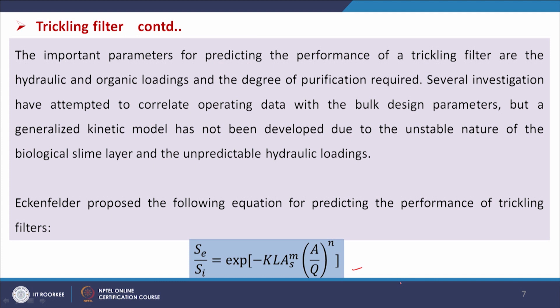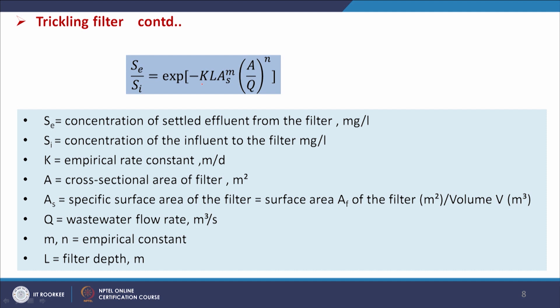Here we will see one empirical relationship proposed by Eckenfelder for predicting the performance of a trickling filter. The equation is: Se/Si = exp(−K × L × As^m × A/Q^n), where Se is the concentration of settled effluent from the filter, Si is the concentration of the influent to the filter, K is the empirical rate constant in meters per day, A is the cross-sectional area of the filter, and As is the specific surface area of the filter (surface area divided by volume).